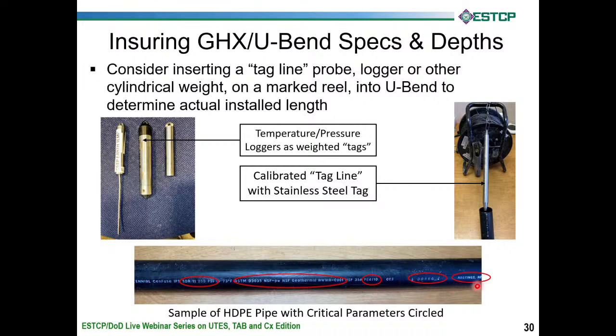Another parameter that's typically printed is the manufacturing location. HDPE is still made in America, and it's kind of expensive to ship for a low-value product, so you don't get a lot of foreign piping in plastic like you do with steel. But if you require a domestic manufacturer, then the manufacturing location is stamped on there. And then also the polymer mixture that you require, and 4710 is what's usually required today. So the PE resin that's on there is important too. And then you usually require an NSF certification, National Sanitation Foundation, sometimes American Water Works, but always an ASTM number on here. It's important to see that that's there.